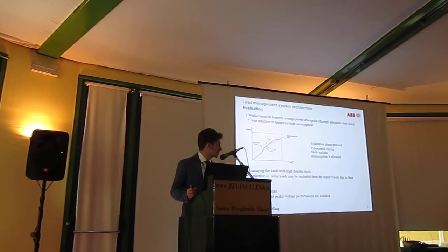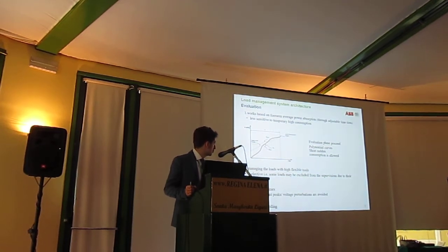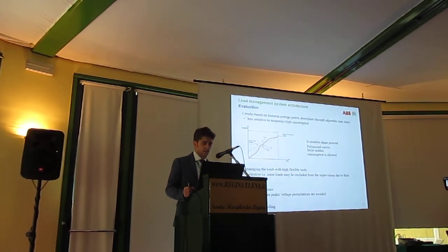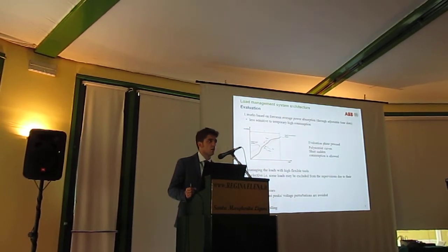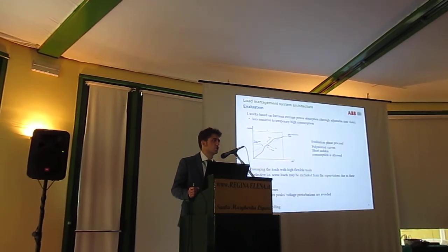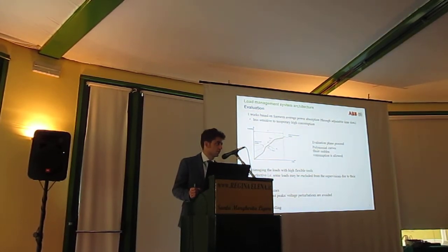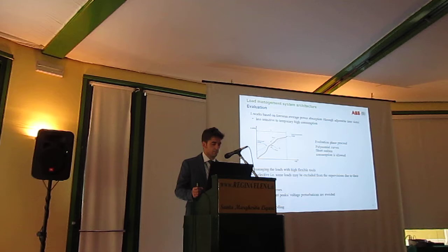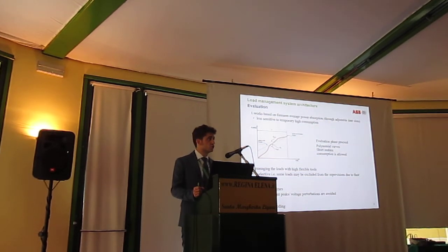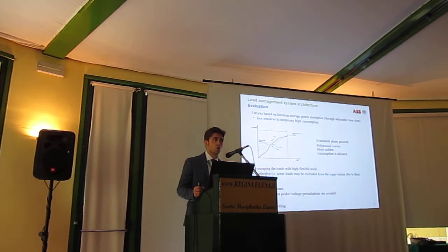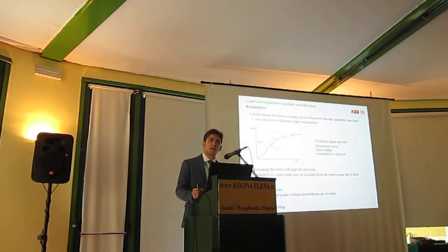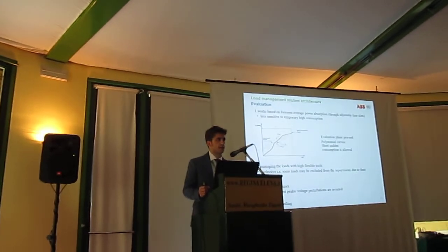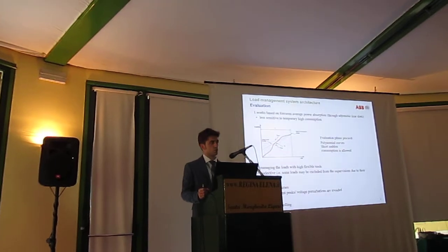I'd like to point out some other tools which are provided by the controller. I should name the selective feature: it's not mandatory to include all the loads in the power controller cycles. Like an elevator, you can exclude some loads from the cycle. Priorities: you can assign priorities according to the importance of the load, so as to disconnect some loads as late as possible and as little as possible, like an industrial refrigerator, where the foods can be spoiled.